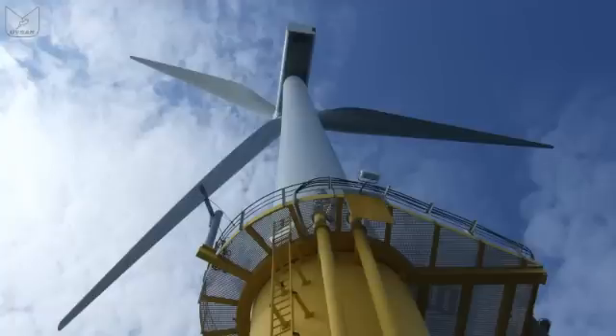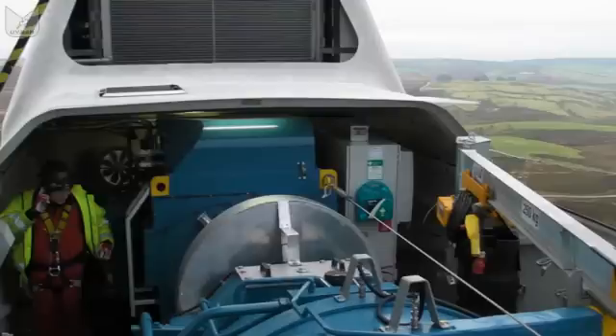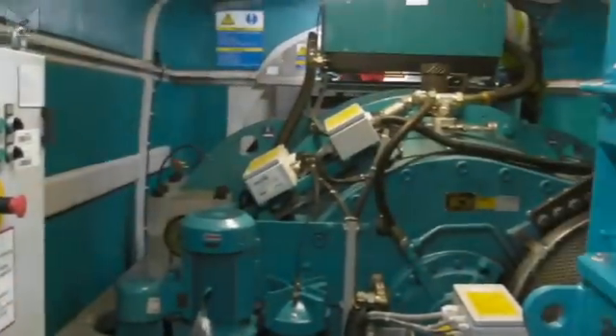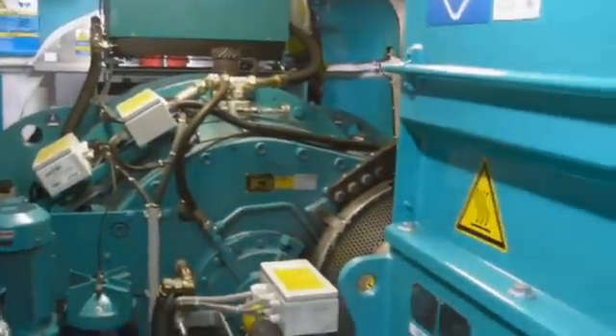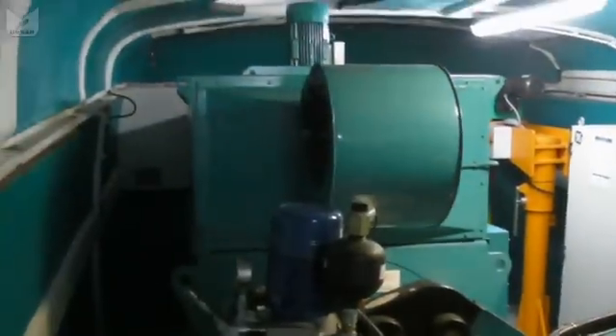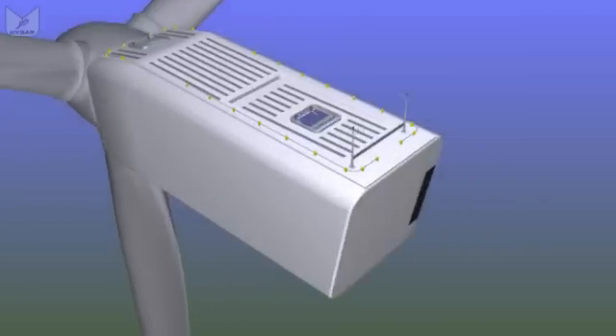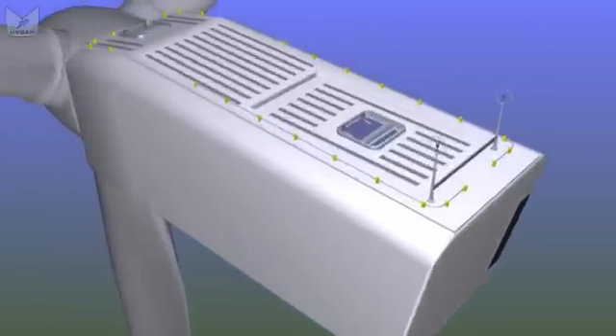The layout of a multi-megawatt nacelle is again more variable than for a smaller version. We always have to have a generator, but we may not have to have a transformer. In a few cases, such as the famous Enercon egg-shaped nacelle, we don't even need a gearbox. They're direct drive, we just have a shaft linking to a motor, and then lots of extremely complicated electronics to condition that power for connection to the grid. But in most cases, we need the same as we needed in the small turbine. Gearbox, generator, possibly a transformer, all in a fiberglass box. And in our example, we're looking at a typical design used by a number of manufacturers, where we have a nacelle that's three meters high, two and a half meters wide, seven or eight meters long. It's a fiberglass box about the size of a site hut.